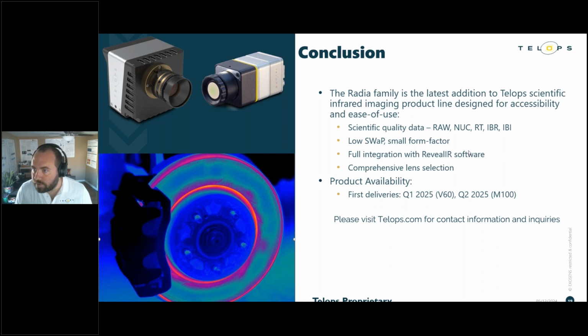Let's see, one more question just came in. Difference in sensitivity to ambient temperature. Yes, that's a good point. That's a good distinction between the cooled and uncooled technologies. The uncooled camera, as you can imagine from the name, the detector does not have any cooling on it, and as such, it is sensitive to the ambient temperature in the environment in which it's being operated. So with the V60, for example, we recommend setting up the camera and letting it run for 30 minutes before taking any measurements. But with the M100, we've got the cooled detector, so we've got thermal compensation for the ambient temperature built into that camera. So you don't have to worry about that with the M100.